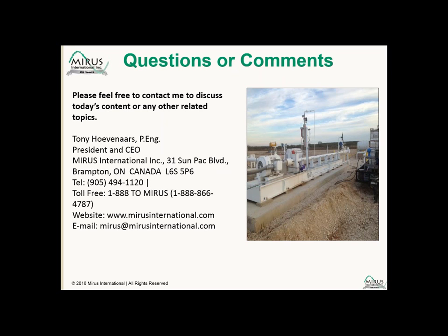Okay, the second question is, what if the generator supplies single-phase loads or phase-to-neutral loads? Good question. This particular application was a three-phase load, and a three-phase nonlinear load is going to generate 5th, 7th, 11th, and 13th harmonics, as I introduced early on in the webinar. When you're dealing with single-phase phase-to-neutral loads, you'll now have the addition of third harmonic components. These will also load down the generator, also require that the generator be oversized, also increase fuel consumption.